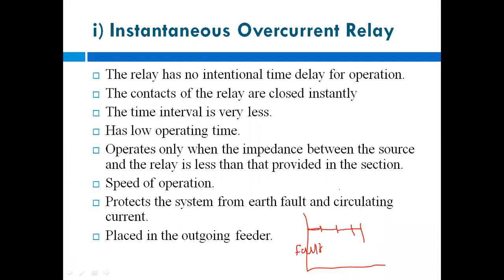But this instantaneous overcurrent relay has no intentional time delay. What we are actually doing is setting a minimum operating time, from 0.3 to 0.5 seconds. This is the minimum operating time of the relay. But for this instantaneous overcurrent relay, no time is provided for the operation, so its contacts get instantly closed.